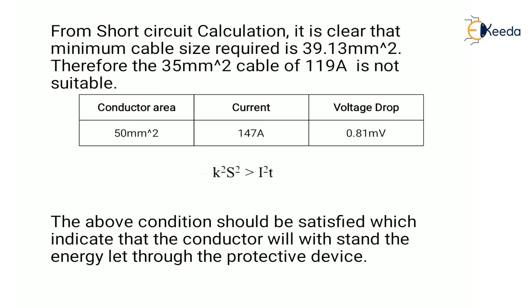Since the 35 mm² cable does not satisfy the short circuit condition, we select the next higher value from Table 15: conductor area 50 mm², current carrying capacity 147 A, and voltage drop 0.81 mV/A/m. This will satisfy the condition, indicating that the conductor will withstand the let-through energy of the protective device.